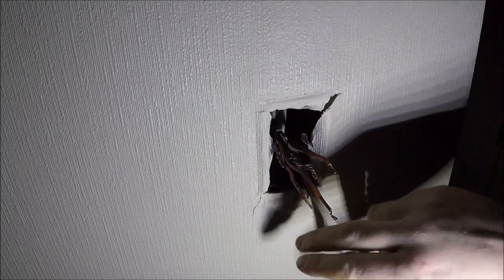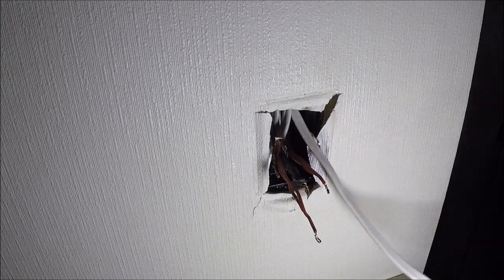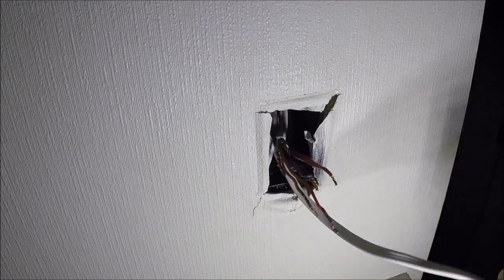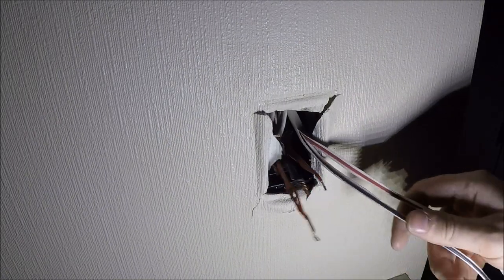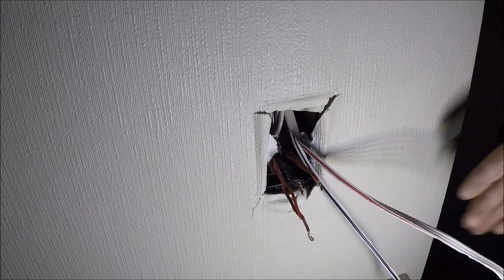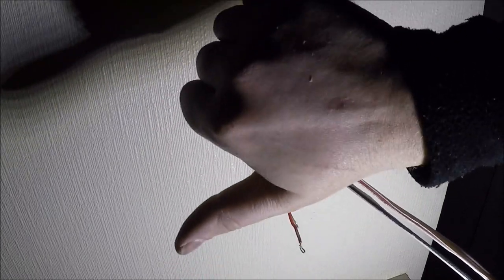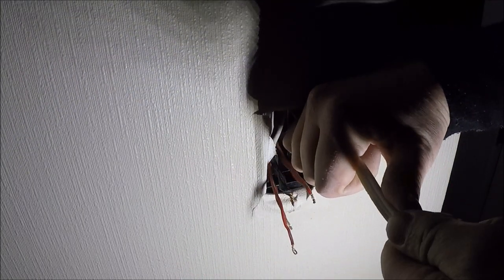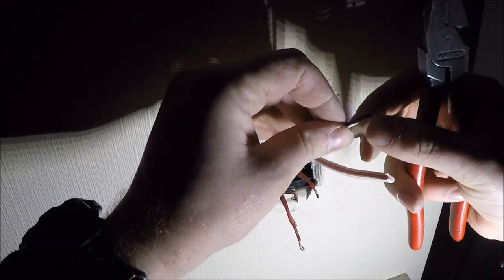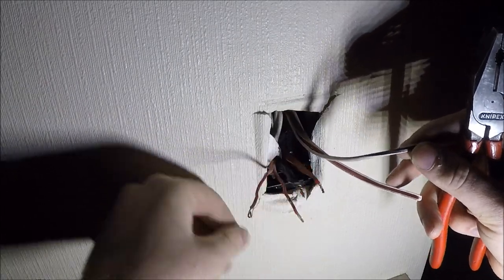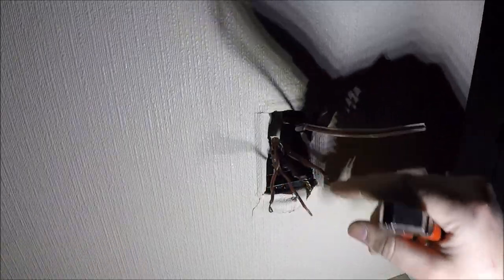So off camera, as I said, I was throwing a plastic flush box in just because they're a bit easier to work with. Now my cables are here. This cable here, I found a whole lot of excess length in behind the flush box. So I'll peel the cores back and re-terminate them close to the connection. Now, the best way to measure length out of a flush box is to do a hand and a thumb width. So out like that. Snip it right there. Whip the insulation off. Now this one was number two, this cable, just because I know my feeds still there and I've got three in one.